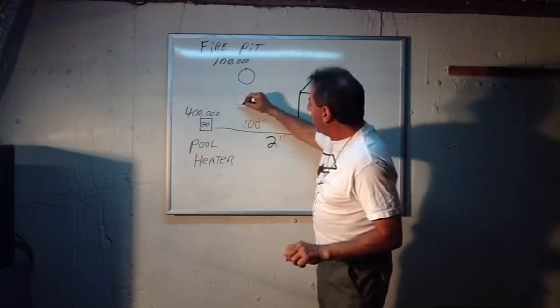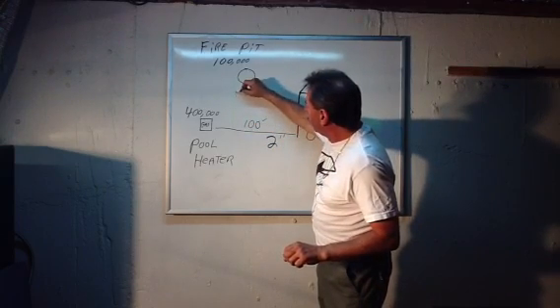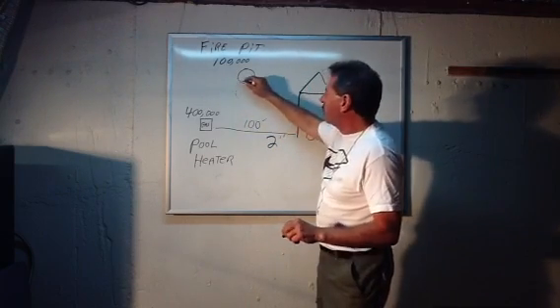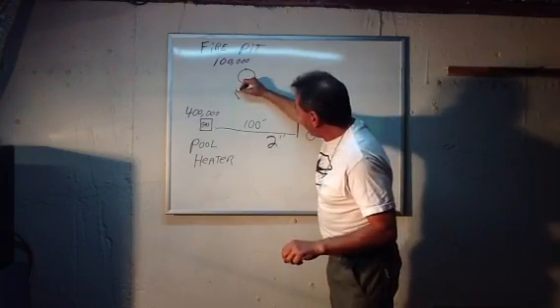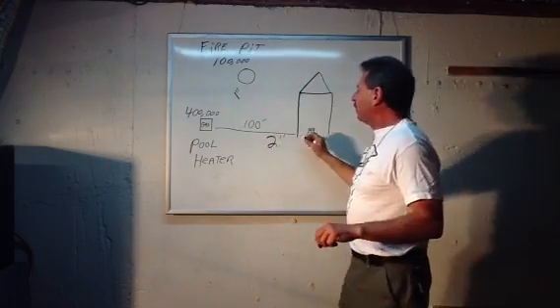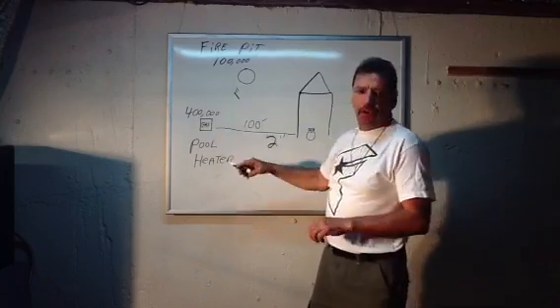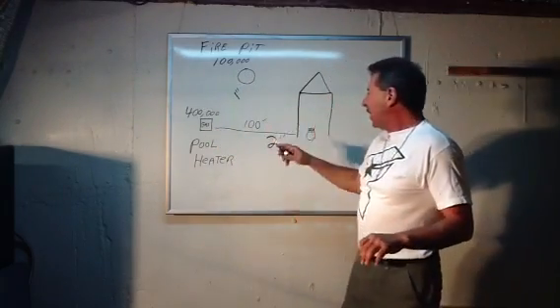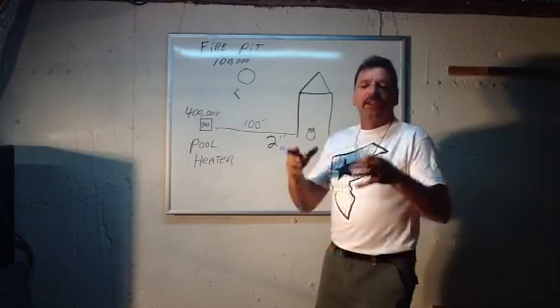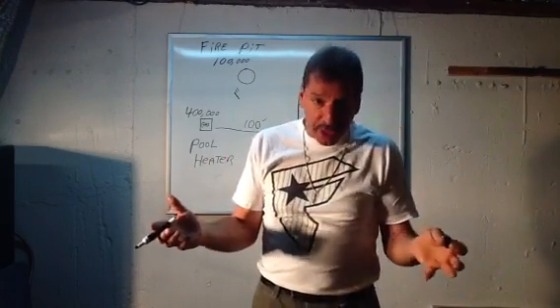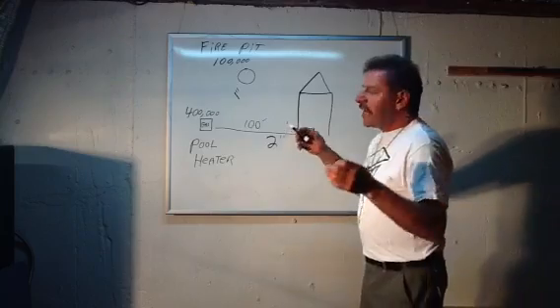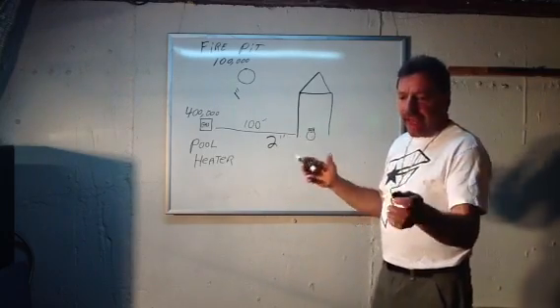And then I broke it down to 1 inch going down to the fire pit because that was small. It was a short run and it was only 100,000 BTUs, so that could be broken down to 1 inch. But that supplied me with 800,000 BTUs, way more than enough for the pool heater and the fire pit. Inch and a half was just a little too short, but the next size up is 2 inch. There is no inch and three quarter. So that's basically how you do the math for that and that chart.